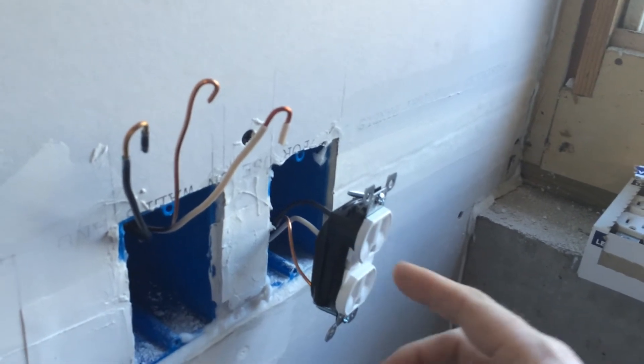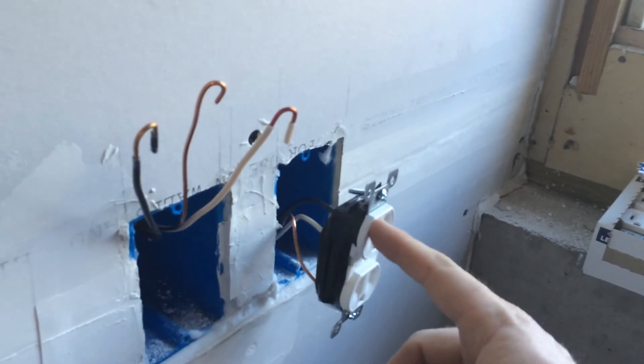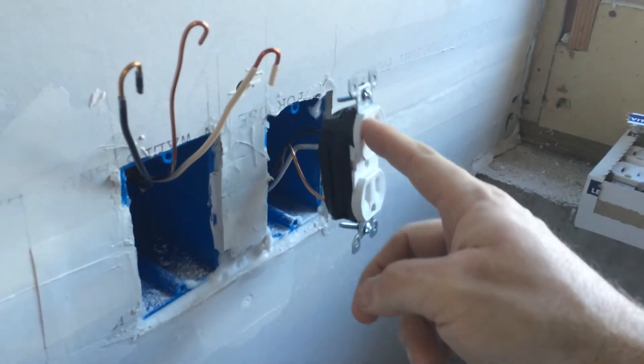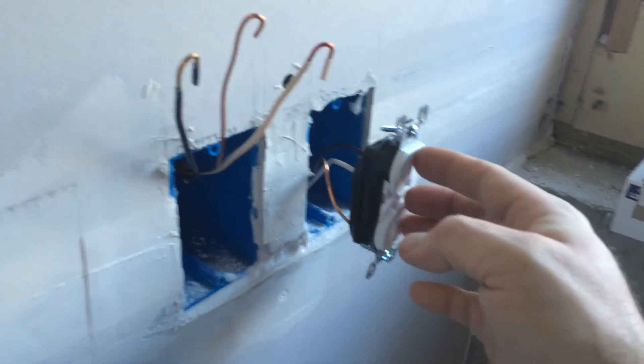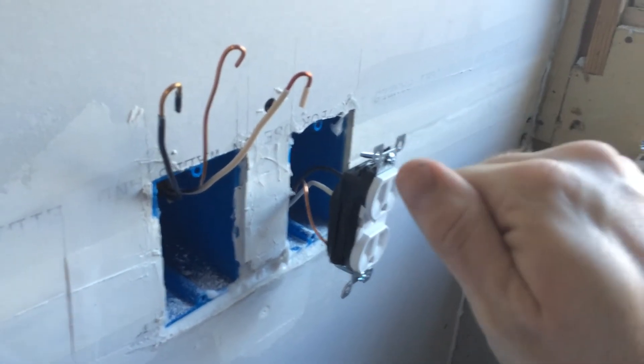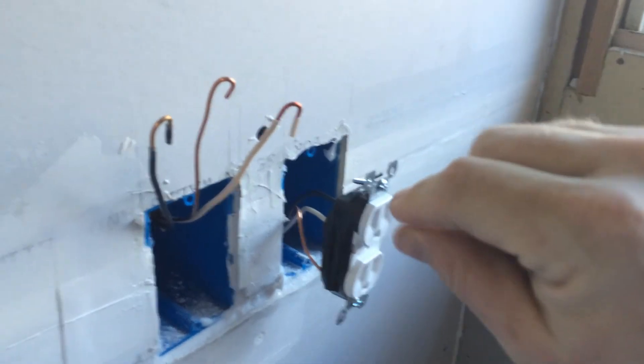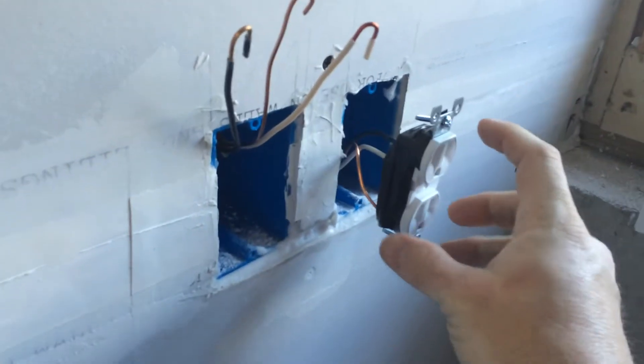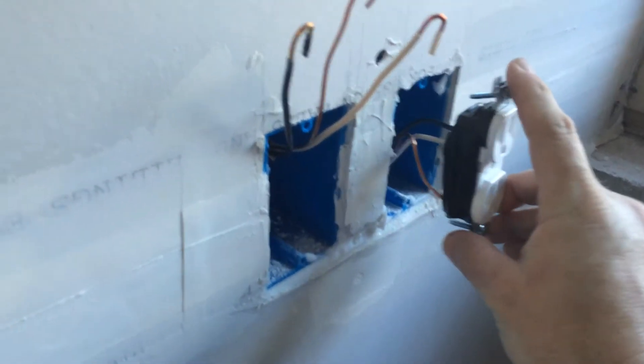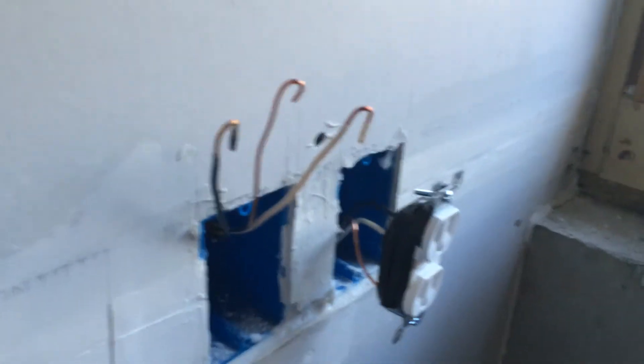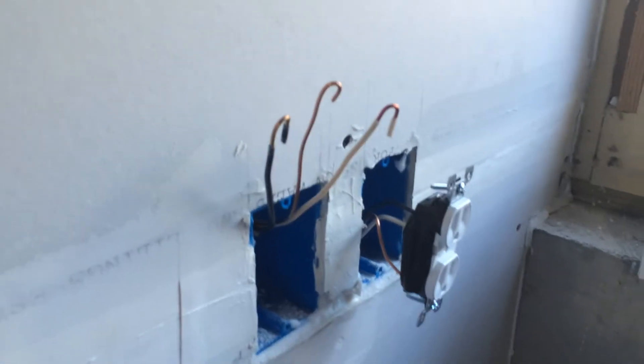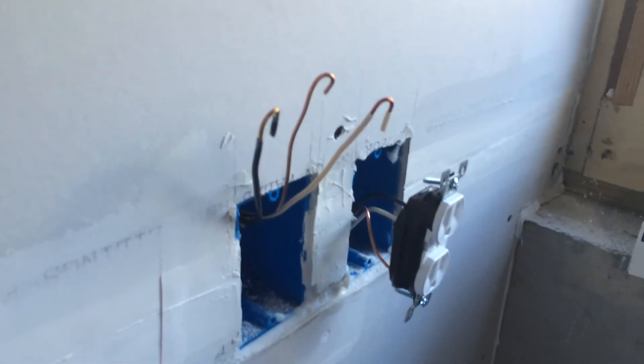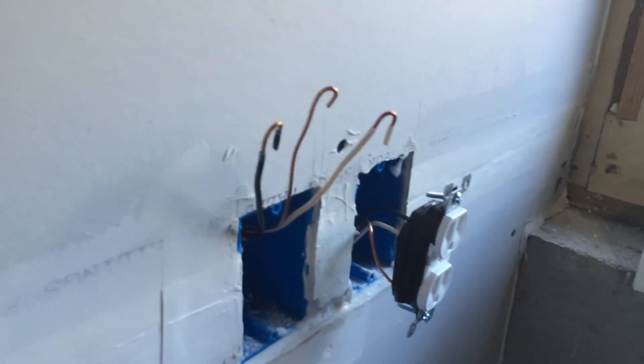These are cheap residential receptacles. They are what's called a backstab, so you can strip a little bit of wire and shove them in the back. I don't ever recommend doing it that way. I don't want to say if I had a dollar for every time I've been called into a person's residence to fix something like this, because I do service calls.